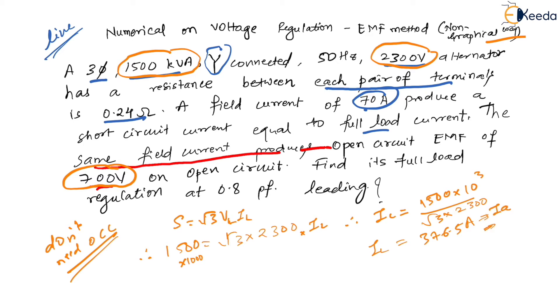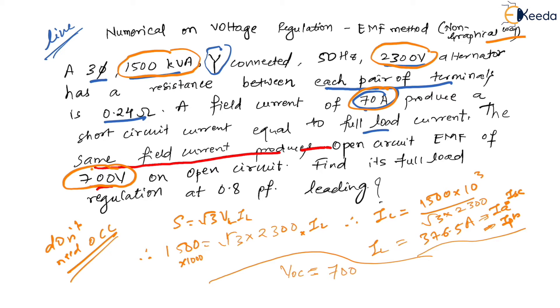This IL = 376.5 A is the rated current, which is also IA (armature current), phase current, and ISC (short circuit current). This short circuit current occurs at a field current of 70 amperes. Now, the open circuit voltage VOC is 700 volts, but that is a line value. For phase value, divide by √3, since all given values are line values unless otherwise specified.